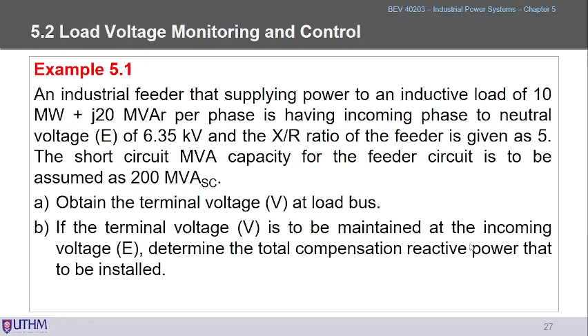It seems like the V square over S, like you are finding the base impedance. So E is 6.35 kV, and S is the short circuit capacity, 200 MVA. So per phase it is 0.2.